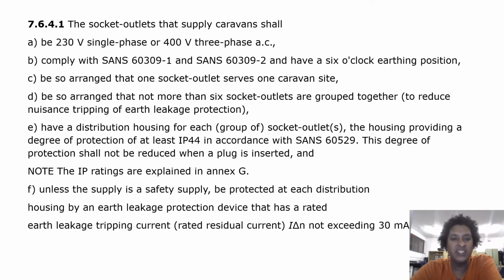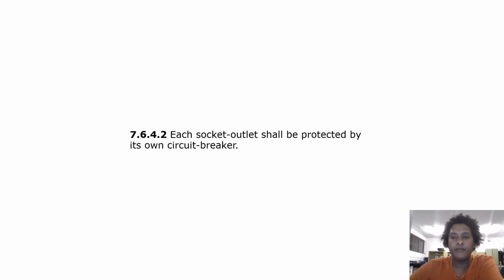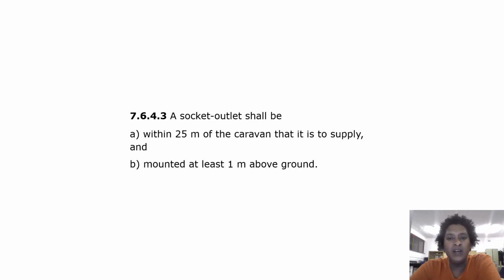This degree of protection shall not be reduced when a plug is inserted, and note the IP ratings are explained in Annexure G. Unless the supply is a safety supply, they shall be protected at each distribution housing by an earth leakage protection device that has a rated earth leakage tripping current not exceeding 30 milliamps. Each socket outlet shall be protected by its own circuit breaker. A socket outlet shall be within 25 meters of the caravan that it is to supply and mounted at least 1 meter above ground.